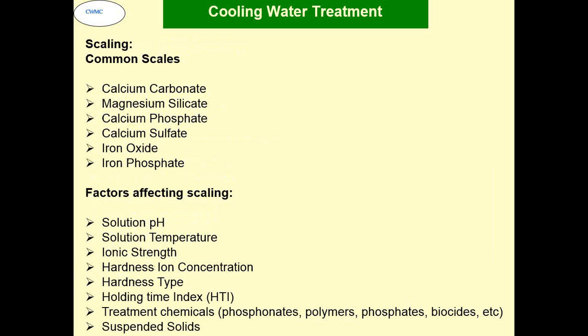Scaling: common scales are calcium carbonate, magnesium silicate, calcium phosphate, calcium sulfate, iron oxide, iron phosphate. And the factors which affect the scaling, basically, scaling is essentially precipitation of the dissolved solid at higher temperatures. So factors affecting scaling are solution pH, solution temperature, ionic strength, strength of ion, hardness ion concentration, hardness type, holding time index, treatment chemicals, phosphonate, polymer, phosphates, biocide, etc. Suspended solids.